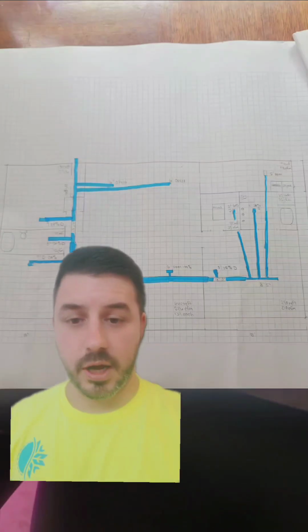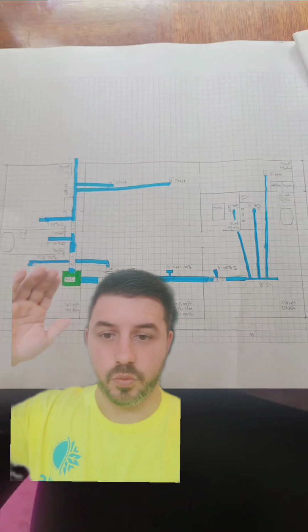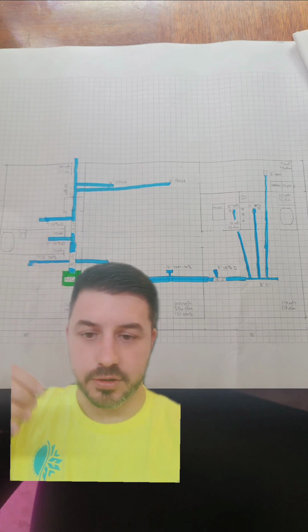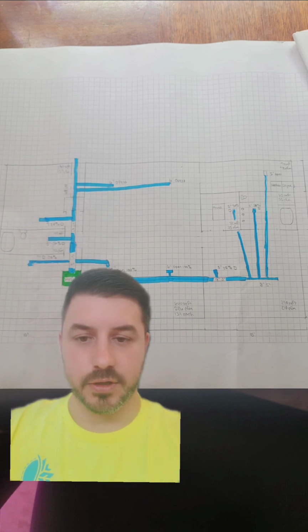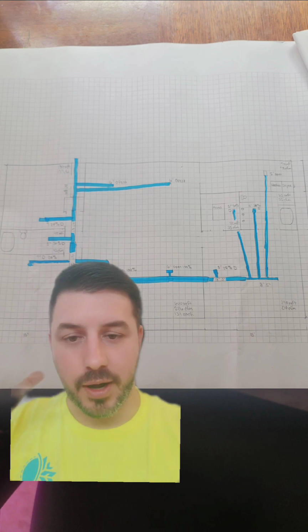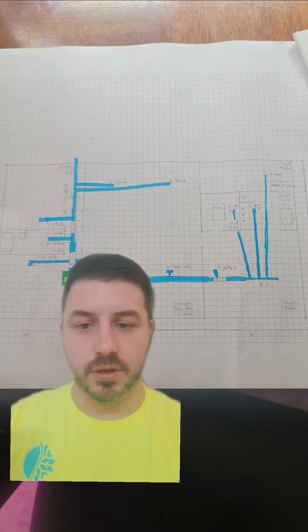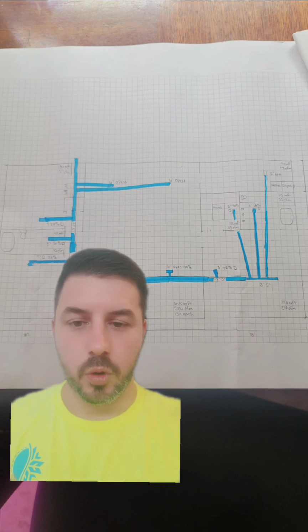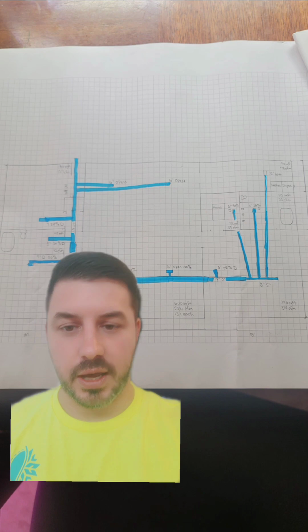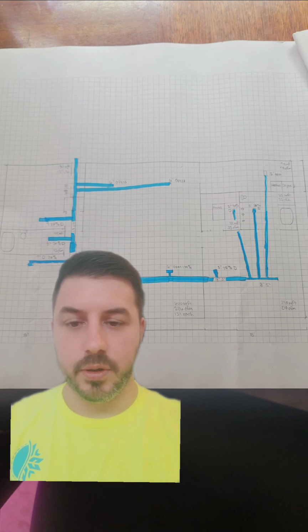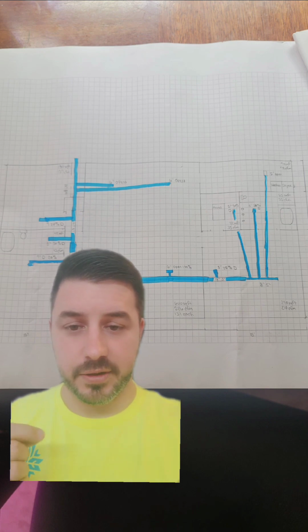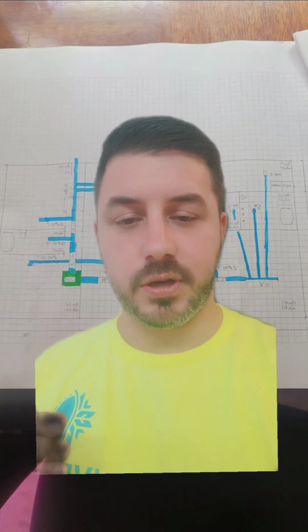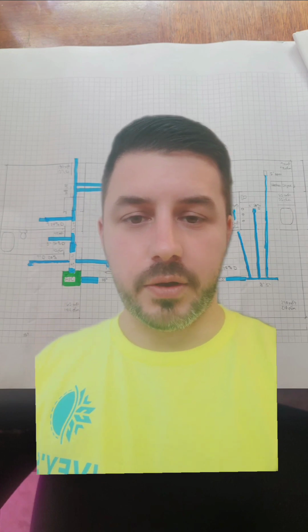capability of this system. Now we're back at the blueprint. Now you can see we can go everything at 0.18 friction rate, and then you could turn your wheel and you could pick all the stuff that you want. Now in my example, I incorporate dampers because it gives us fine tuning capability. Sometimes you'll need more than a 7-inch, but not quite as much as an 8, and you can actually damper it down. There is a way to actually figure out exactly the exact percentage that you need to damper it down. The reason I tell everyone the maximum is because some people don't care about noise.